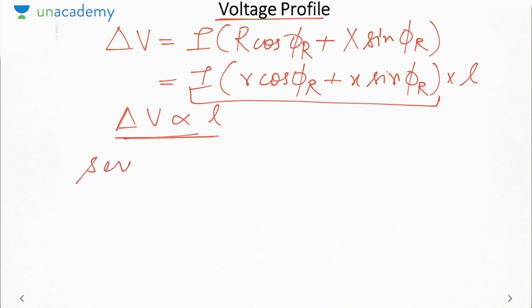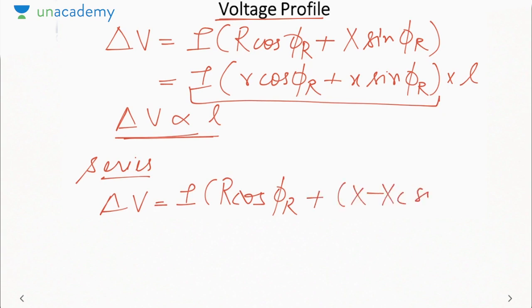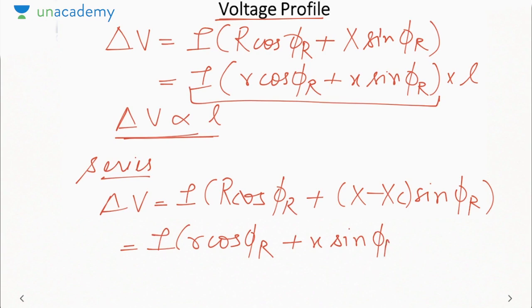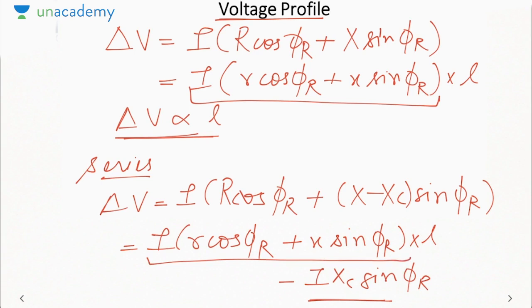In case of series, what we were doing is delta V was I into R cos phi R plus X minus XC sin phi R. So that will be I into, writing in the same way, R cos phi R plus X sin phi R into length minus I XC sin phi R. So this is just a shift in the curve as the slope of the curve remains same. So series compensation provides a shift in the characteristics, whereas shunt compensation changes the slope of the characteristics.